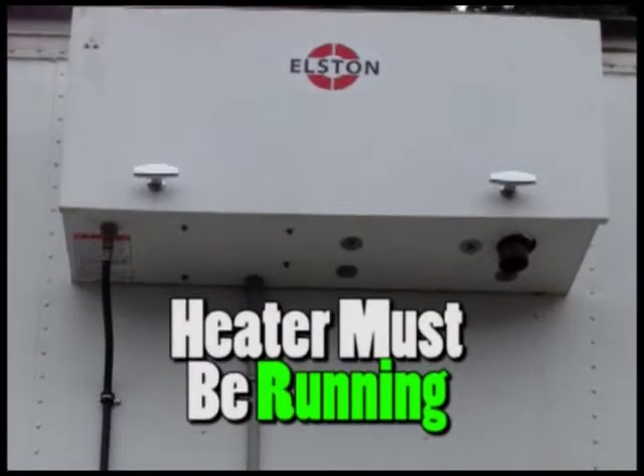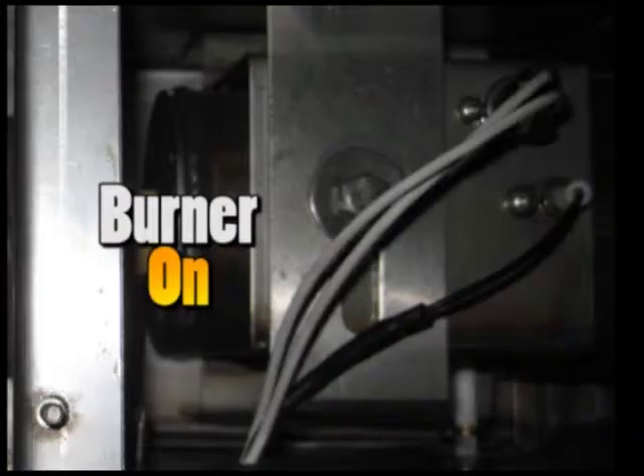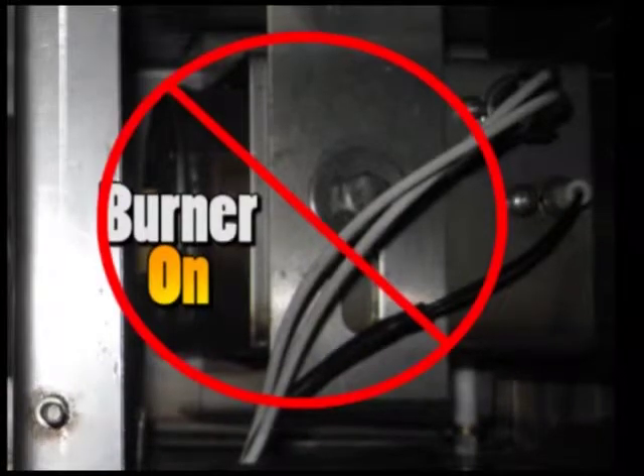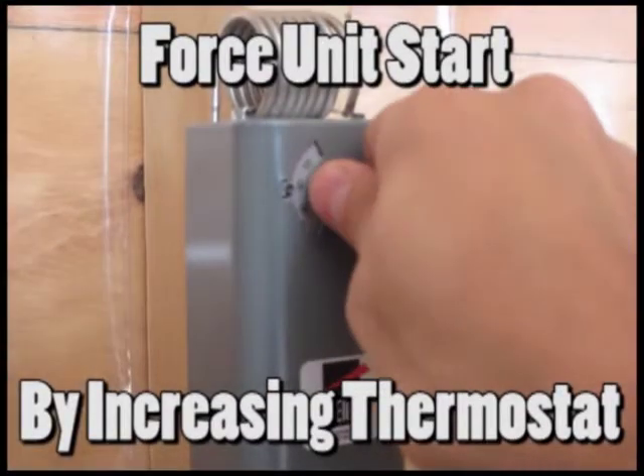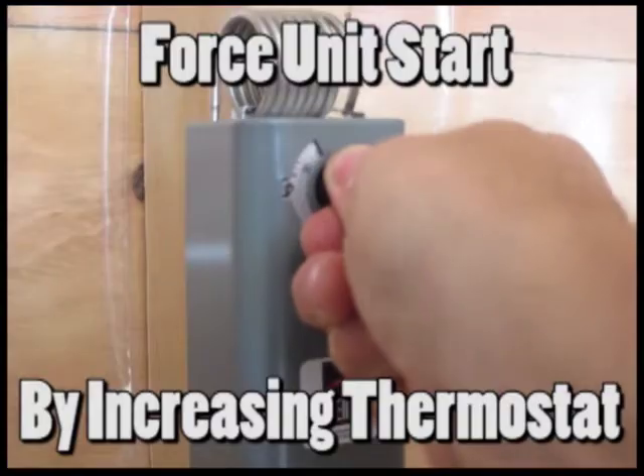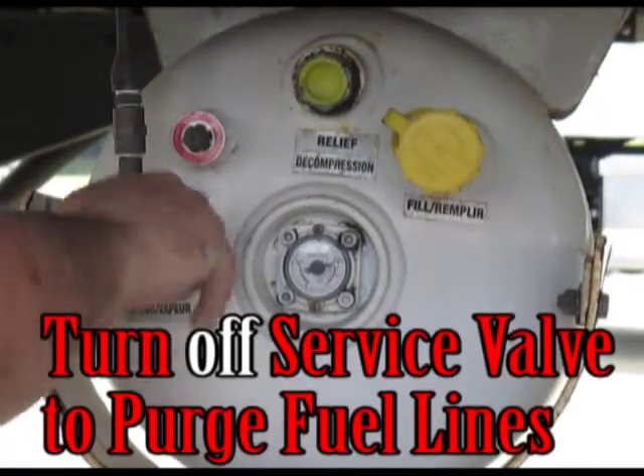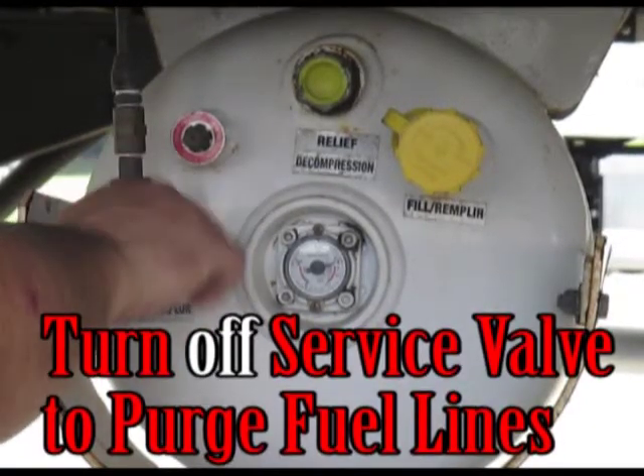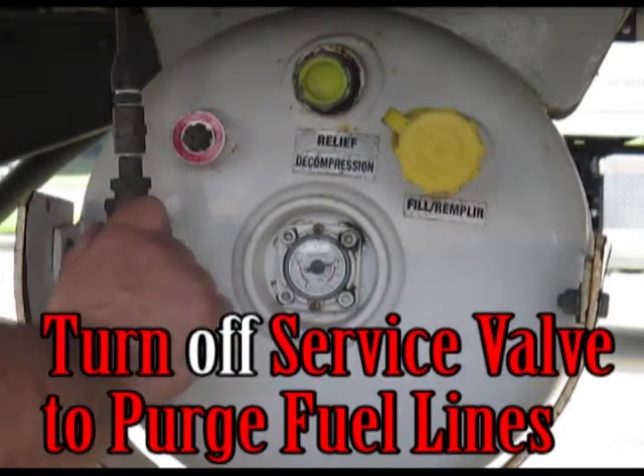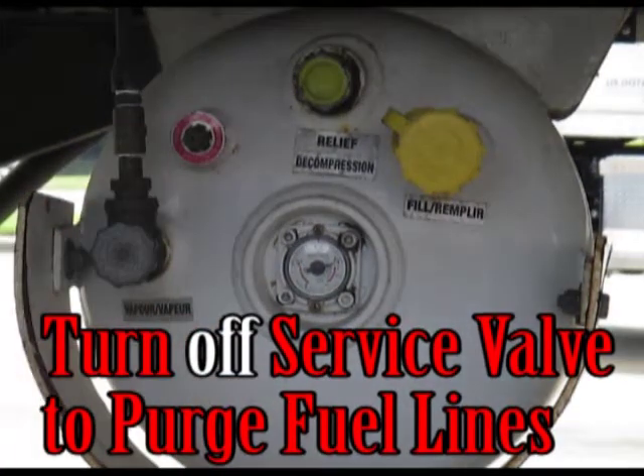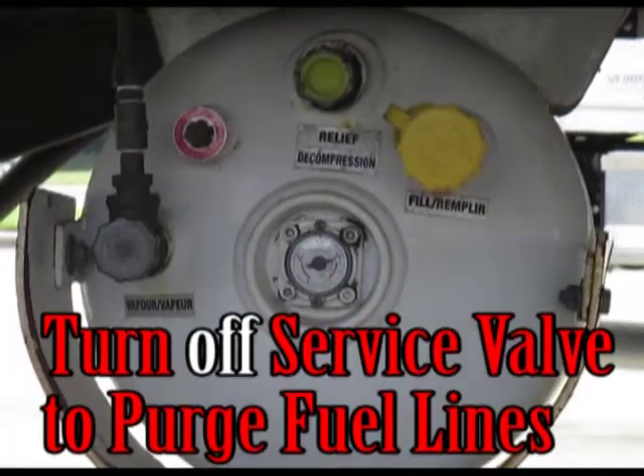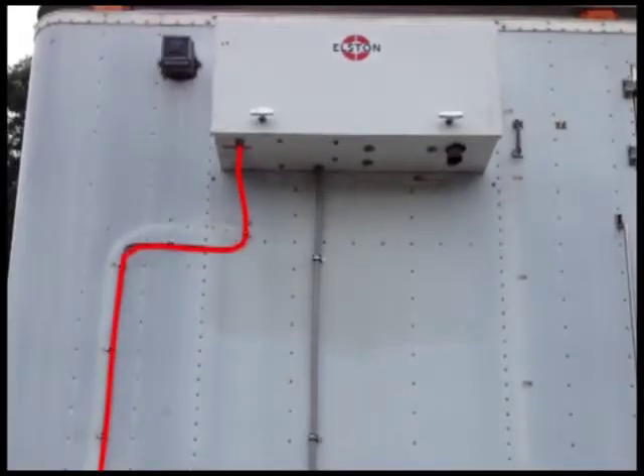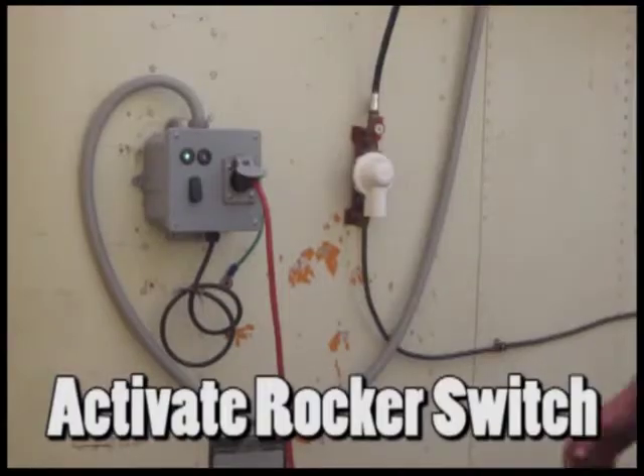To stop the unit, first, ensure that the unit is running and the burner is on. If the burner is not on, force the unit to start by temporarily increasing the thermostat setting. Once the unit is started, close the propane service valve. This purges or removes propane from the fuel line from the tank to the heater unit by burning it off prior to unit shutdown. Once the line is purged and combustion has stopped, turn the rocker switch off.